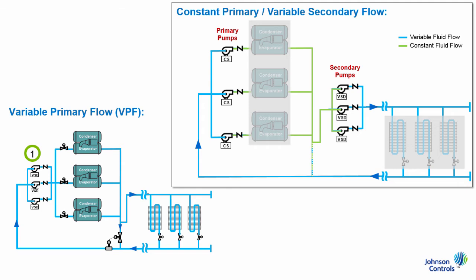Whereas you can see in a primary-secondary system, there are two sets of pumps. They are located both upstream and downstream of the chillers, some of which are constant speed, the primary side, and some variable speed, the secondary side. This difference in design directly links to the higher efficiency and lower install cost for a VPF system.